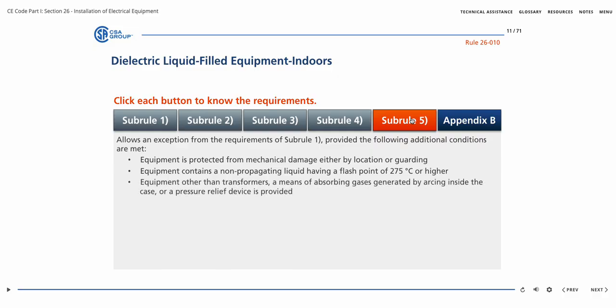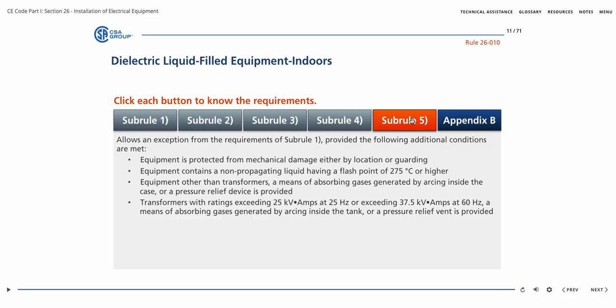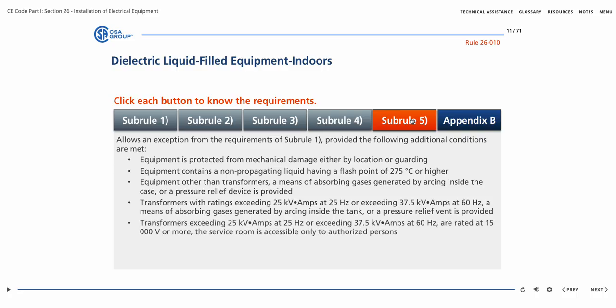For equipment other than transformers, a means of absorbing gases generated by arcing inside the case, or a pressure relief device, is provided. For transformers with a rating of 25 kVA at 25 Hz or exceeding 37.5 kVA at 60 Hz, a means of absorbing gases generated by arcing inside the tank, or a pressure relief vent, is provided. Transformers exceeding 25 kVA at 25 Hz or exceeding 37.5 kVA at 60 Hz are rated at 15,000 volts or more. The service room is accessible only to authorized persons.